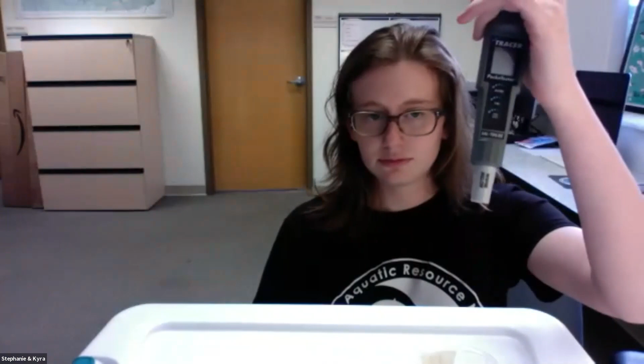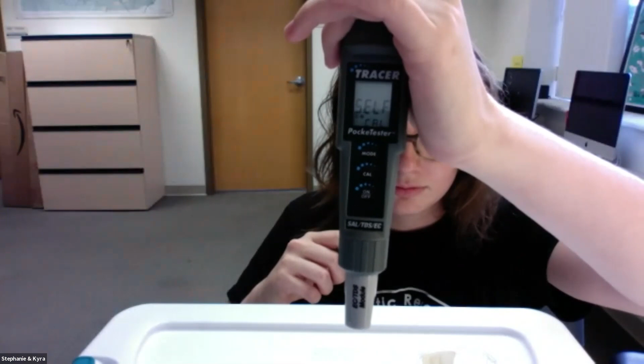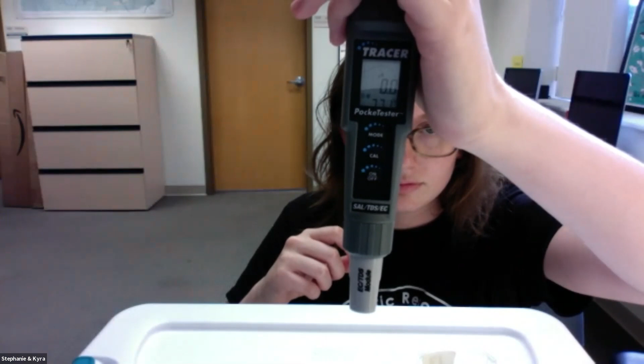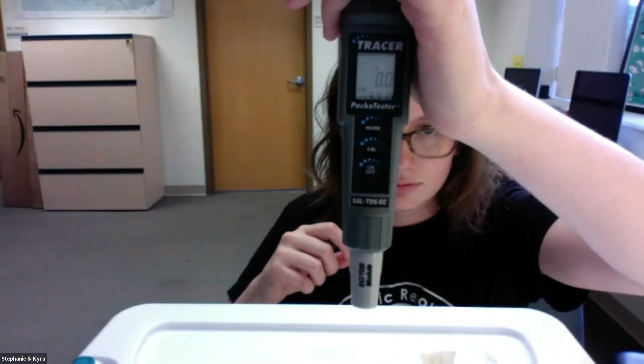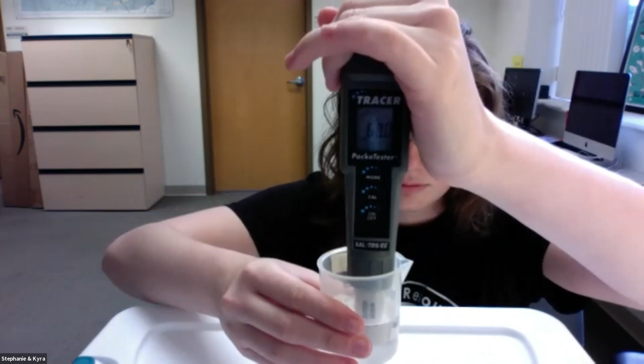Okay, so the first step of the test is to remove the electrode cap and turn your meter back on and make sure it's in the correct setting. It should have the micro Siemens sign there. Okay, as Kyra does. And now the next step is to place the electrode in your beaker and allow the conductivity reading to stabilize. For this test, you'll be looking at the big number in the center of the screen instead of the bottom one. And this may take a moment to stabilize.